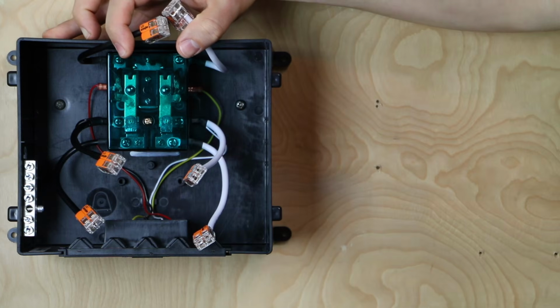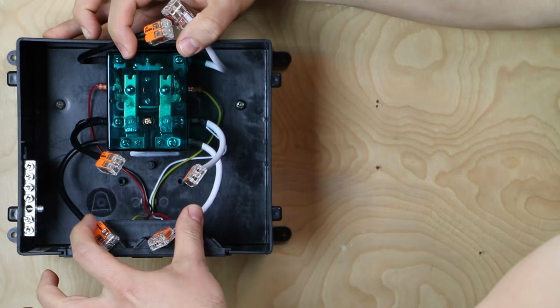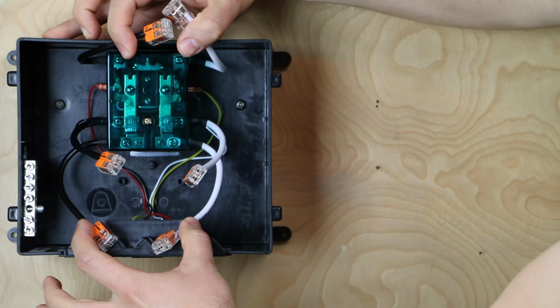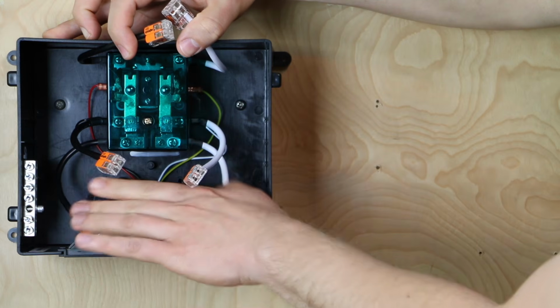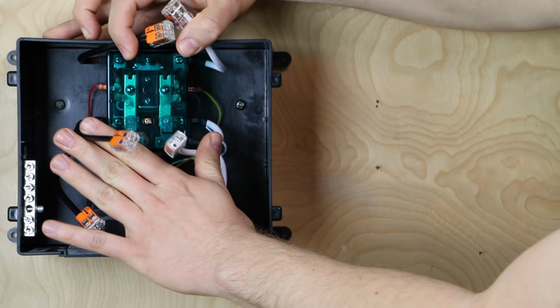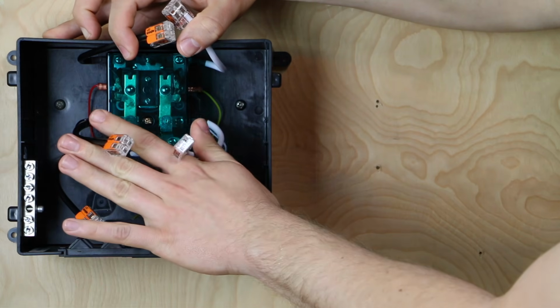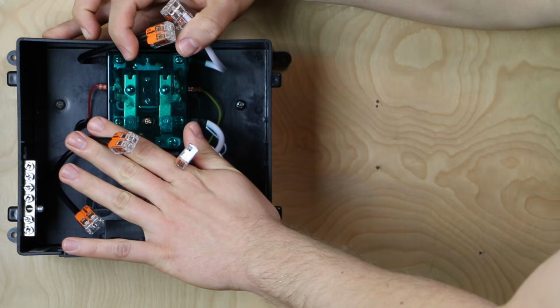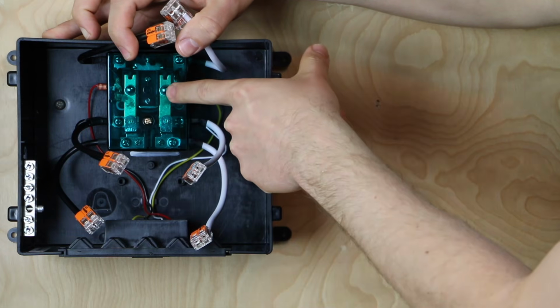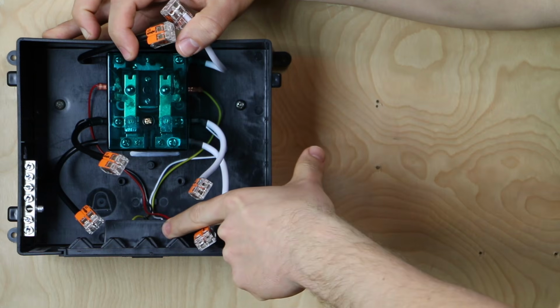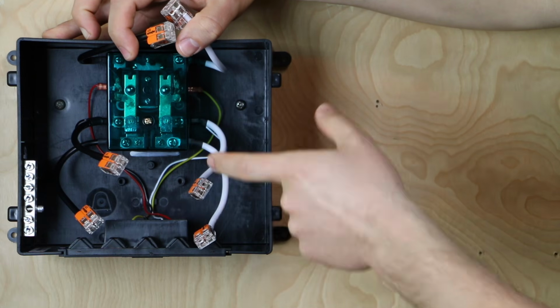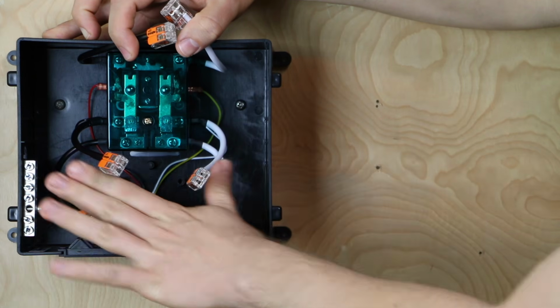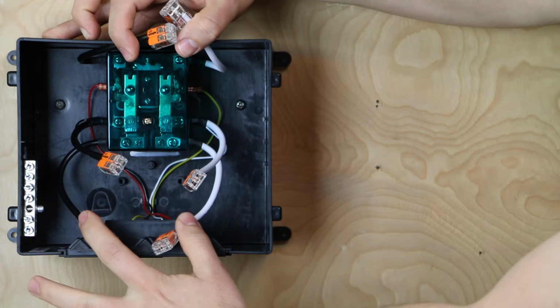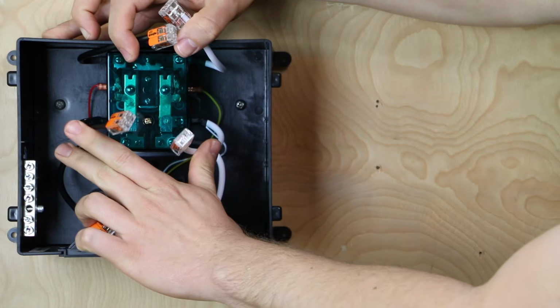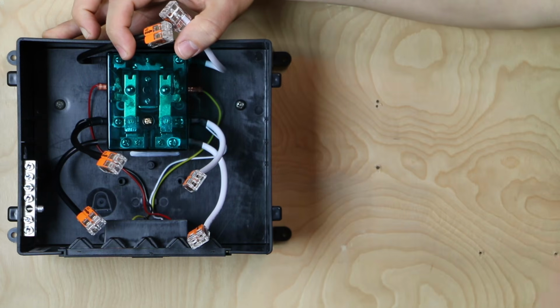What we're going to do is put the inverter on this bottom pair, so that's going to be our default source. Then we're going to put the power grid on the middle pair. So when the power grid is available and energizes this middle pair, the switch is going to detect that. There's a little relay board here, and after about 20 to 30 seconds, it's going to quit drawing power from this pair and start drawing power from this pair, sending it out the top.